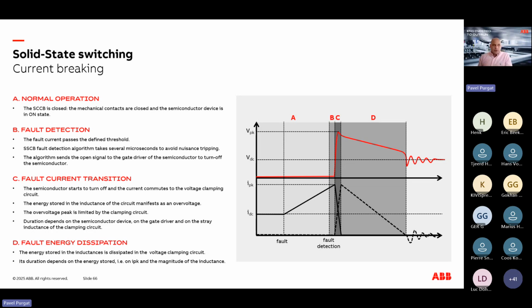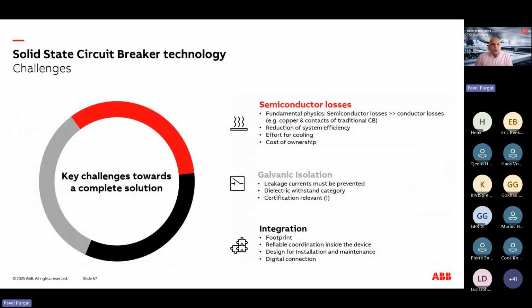After you are sure that you have a short circuit, you turn off the semiconductor, and this is typically very fast and happens within microseconds. When that happens, the current commutes to the voltage absorption unit, or the MOV, as a typical choice, and we have some overvoltage happening. But this overvoltage is, of course, limited by the voltage absorption unit. The time is usually given by the circuit characteristic, because it is given by the amount of energy that you need to dissipate. So what are the challenges that we need to overcome when designing a semiconductor circuit breaker?